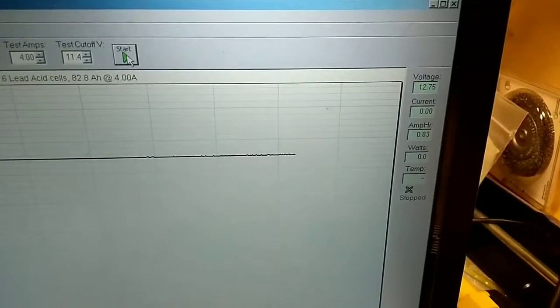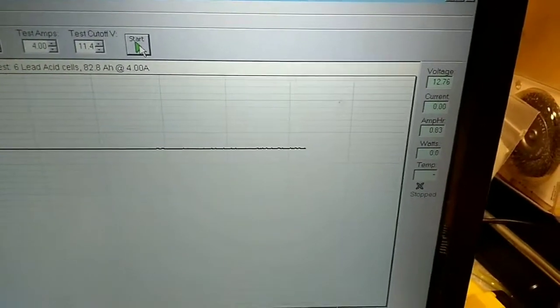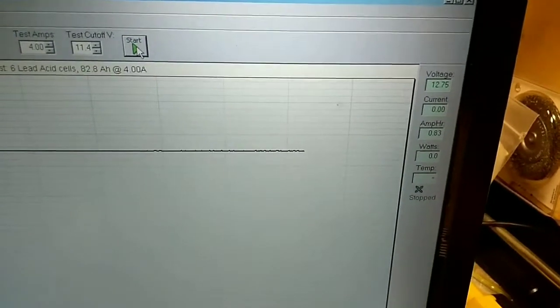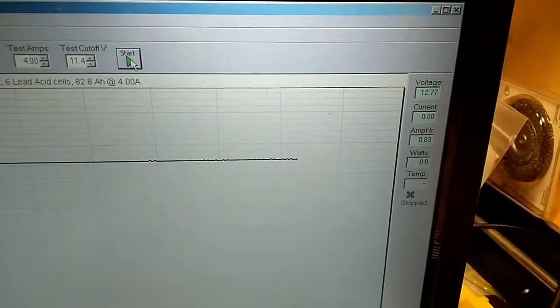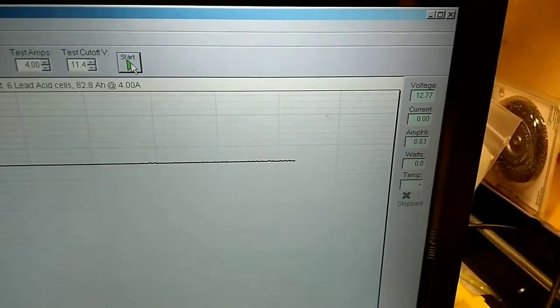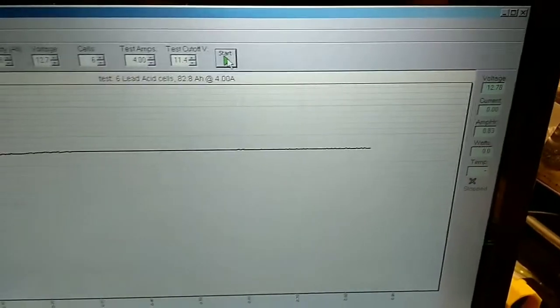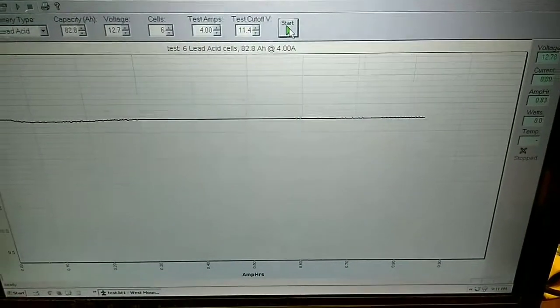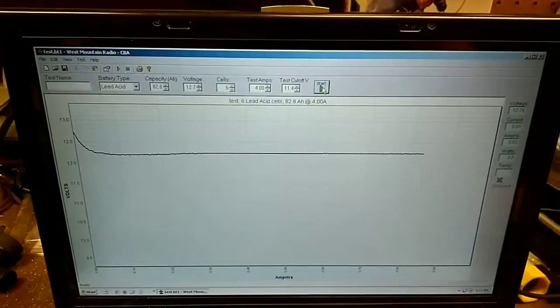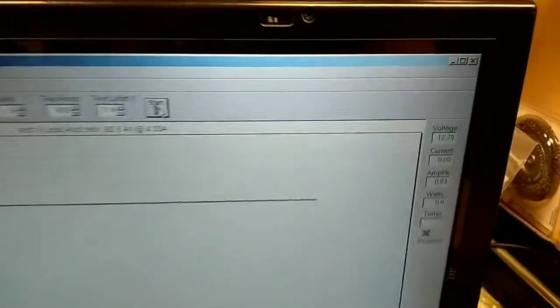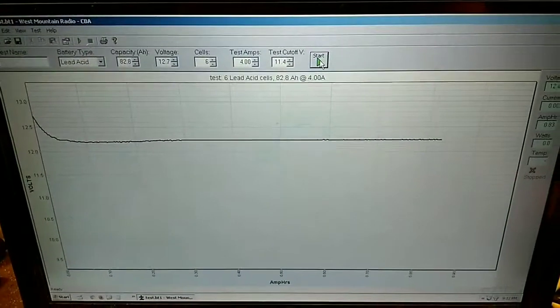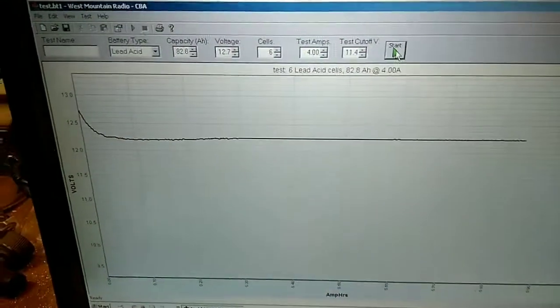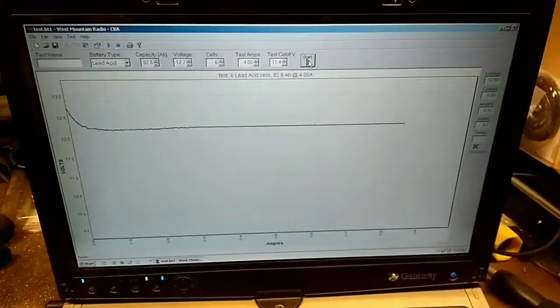So there we are, I think we've pretty well stabilized at about 12.7. That brought it down, that 1% of charge brought it down from the 13.05, 13.6 which was almost nearly directly off the charge, down to about 12.7, 12.77. I'm still not quite there, it really should be about 12.70. I think generally for our situation this will probably be okay. What I intend to do is actually start the test over. This graph will go away, it'll actually restart to a fresh graph, but it was really there to show what a loaded voltage looked like. I do anticipate that there's a possibility this battery is bad. I was a little shocked at how low 4 amps was able to drag the loaded voltage, but the only way to know is to do an amp hour capacity test.